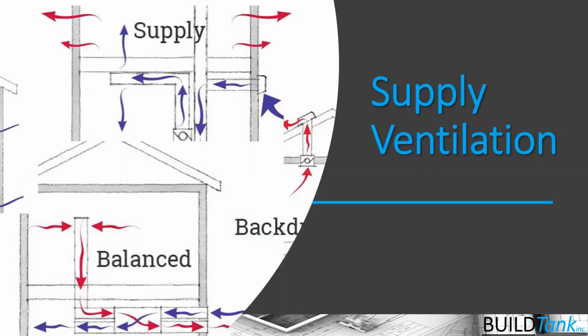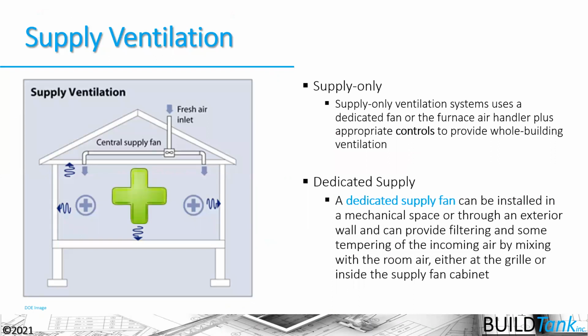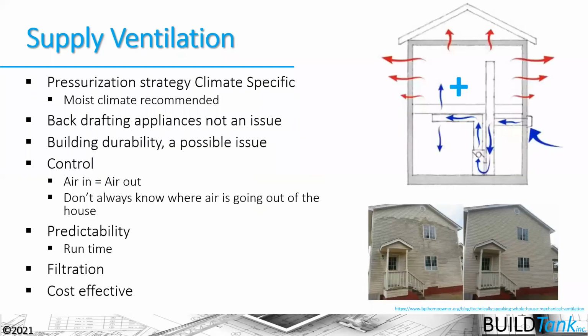The big thing to know about supply ventilation is that it is a positive ventilation strategy, which means it's positive pressure. We're pushing air into that house, and in essence, we're blowing that house up like a balloon. Any air that goes in has to go out of that house. Since we're blowing it up like a balloon, we're pushing air against the building thermal envelope, that boundary that separates conditioned space from unconditioned space, and in essence pushing air through holes in that building envelope. So again, it's important to know: is that air full of moisture and heat? And might there be a problem from doing that?